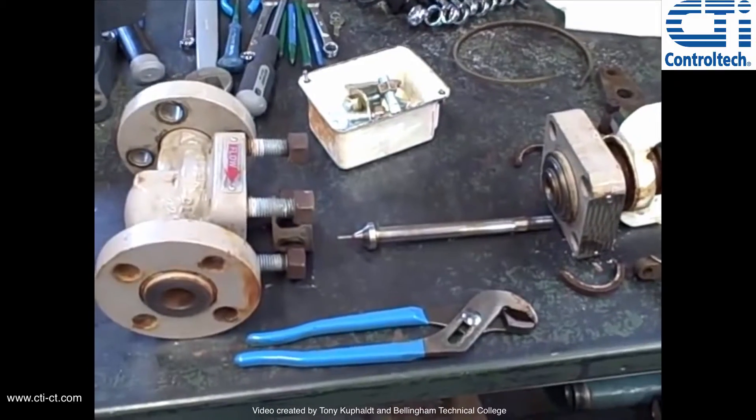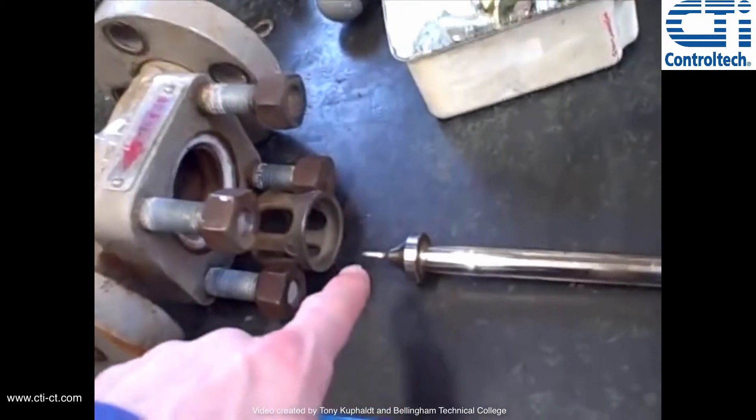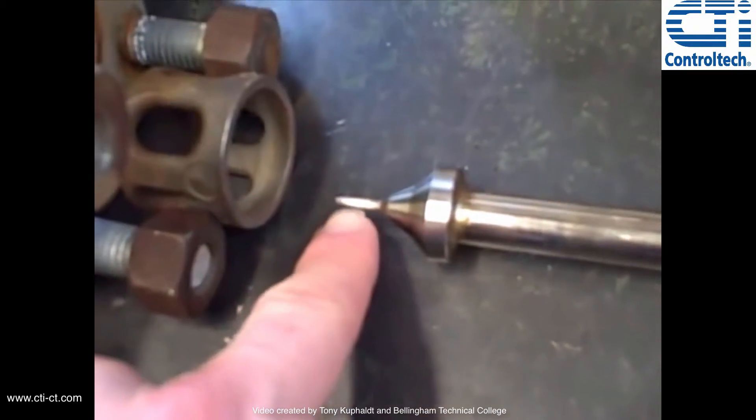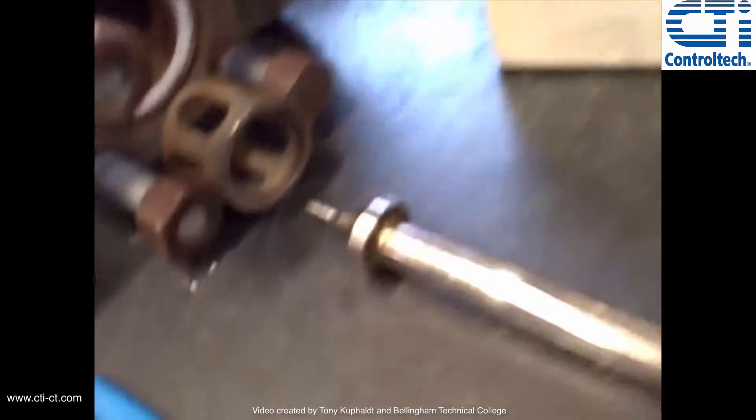Disassembled here on the bench, we have a Valtek Mark One control valve. This is a globe-style control valve. It's got a very small trim in this case — it's a needle-style plug, much smaller than you may expect for other valves of this physical size.